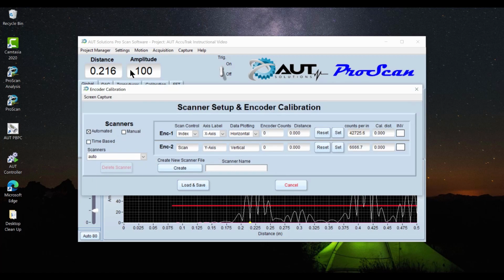So we have our color maps set up. Moving on down, our encoder calibration is automated, so we can go in and verify that here. If you needed to, you can simply measure out the distance, move the scanner that distance, and verify these encoder counts are correct. The encoder counts are actually pulled off of the motors themselves versus a physical encoder, so it's very hard for these to slip. These counts normally don't change. If there is an error and the counts deviate from this, you can either refer to this video or the user's manual for the appropriate scanner counts.